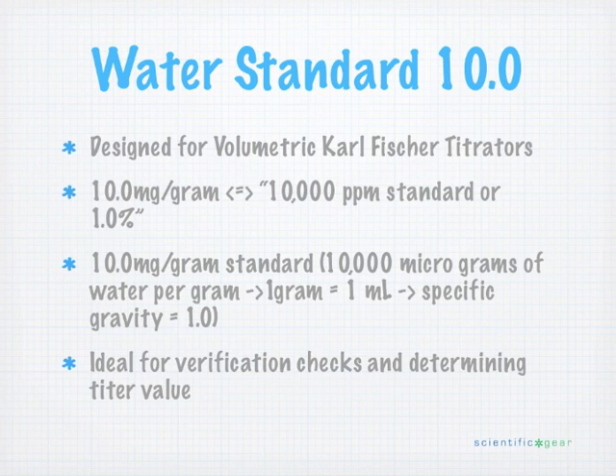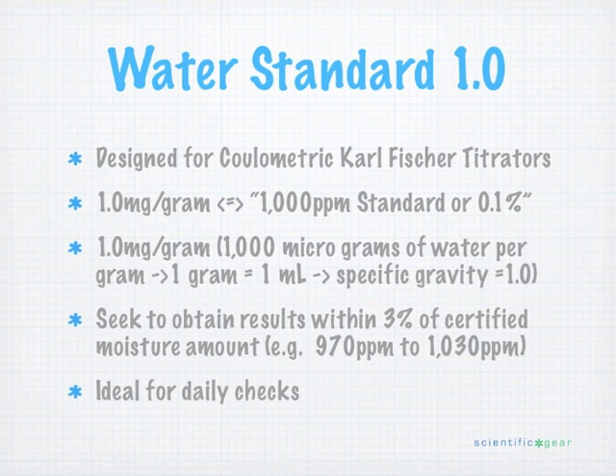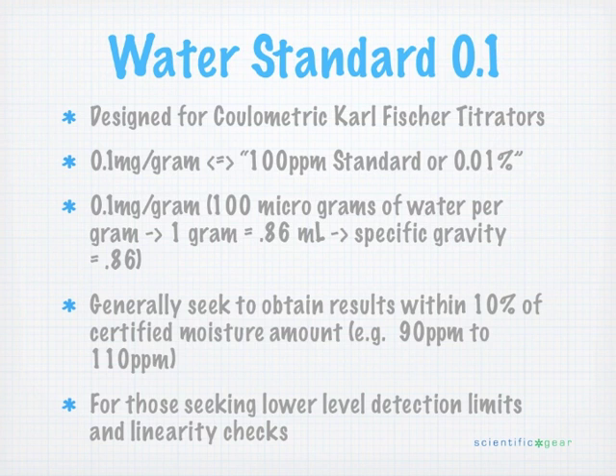On the coulometric side, we have the Water Standard 1, which is a 1 milligram per gram water standard — ideal for a daily check of any coulometer you're working with. We also have our Water Standard 0.1, which is a 100 ppm standard, ideally suited for checking lower limits of detection. Sometimes it's used for linearity checks as well.